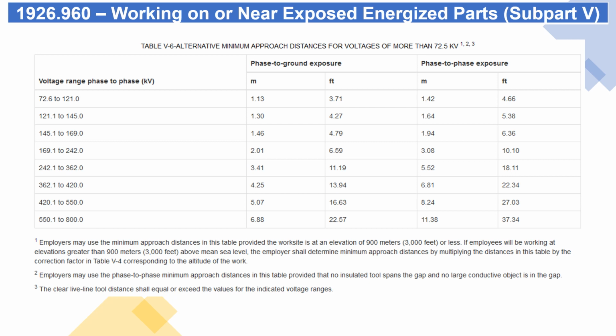Table V6, alternative minimum approach distances for voltages of more than 72.5 kV. Employers may use the minimum approach distances in this table provided the worksite is at an elevation of 900 meters, 3,000 feet, or less. If employees will be working at elevations greater than 900 meters, 3,000 feet, above mean sea level, the employer shall determine minimum approach distances by multiplying the distances in this table by the correction factor in Table V4 corresponding to the altitude of the work. Employers may use the phase-to-phase minimum approach distances in this table provided that no insulated tool spans the gap and no large conductive object is in the gap. The clear live-line tool distance shall equal or exceed the values for the indicated voltage ranges.